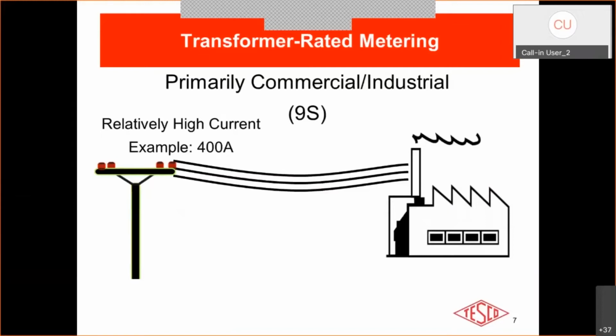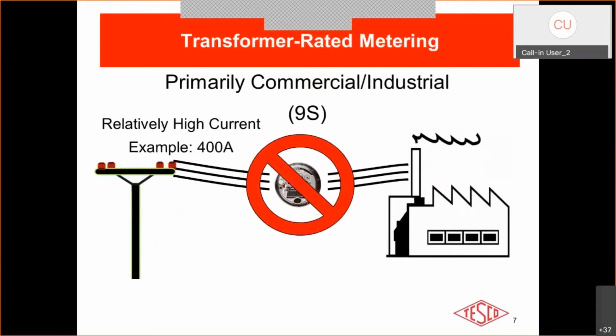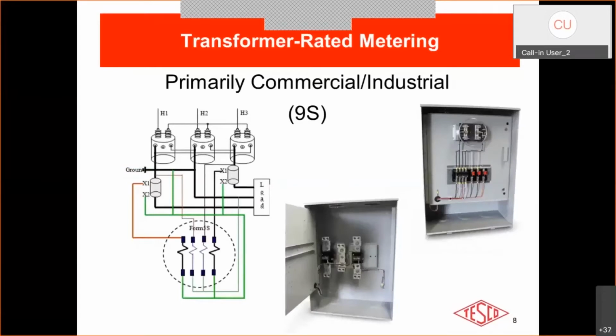In this case, putting a meter in series with the customer load is not applicable. The meter cannot handle that much current. The meter would have to be the size of a Volvo. So putting the meter in series with the customer load in high current applications is a big no-no. And so therefore we have transformer rated metering, or like I like to call it, indirect metering, where we utilize a series of PTs and CTs to ratio down the customer voltage and current to levels that the meter can safely and accurately measure.